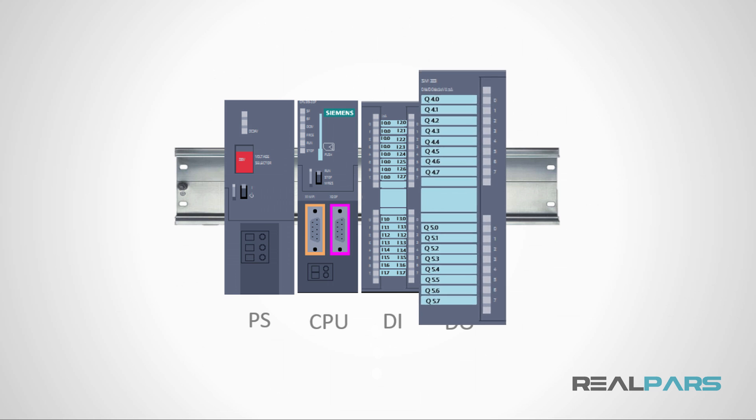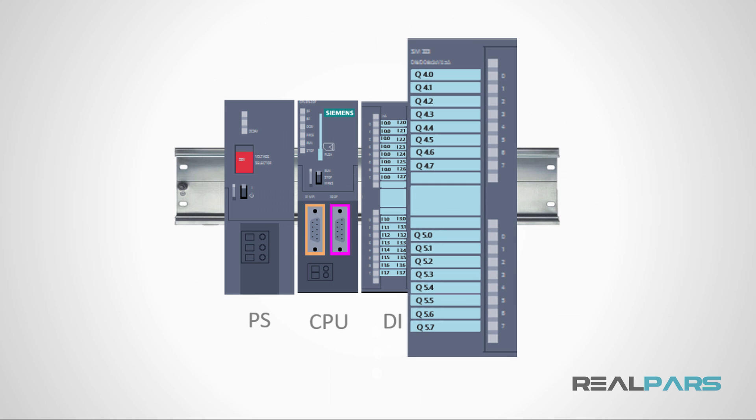Considering these addresses, I can say that the first output's address for this module is Q4.0, the next is Q4.1 and this continues all the way to the last output address which is Q5.7.